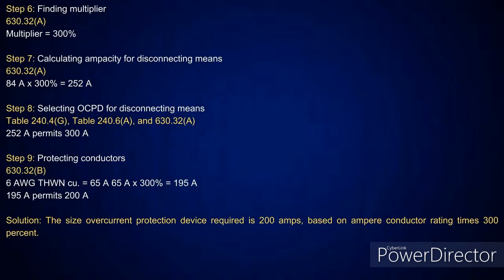The next standard size above that is what? 200 amps. So instead of putting in a 300, I could drop down to the next standard size below that 252 amps. I could have gone to a 250, or I could protect the conductors based on the 300%, which is what? A 200 amp. See the difference there? Most people would go to a 250, but you actually could go to a 200 here.